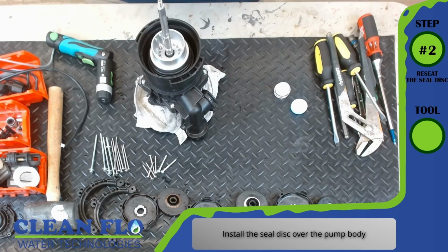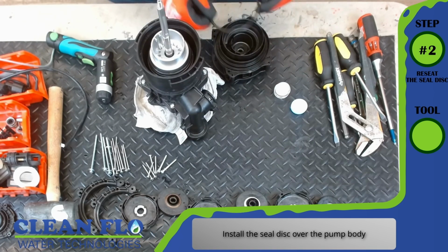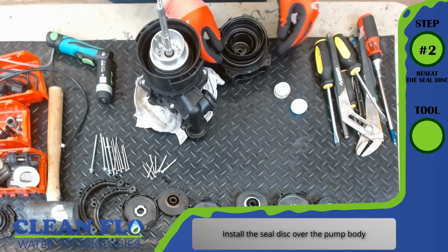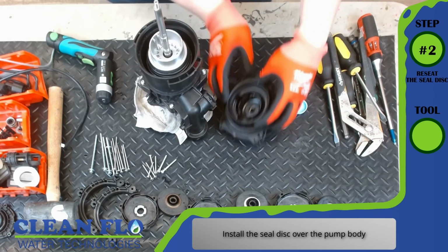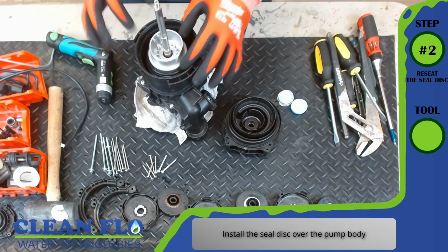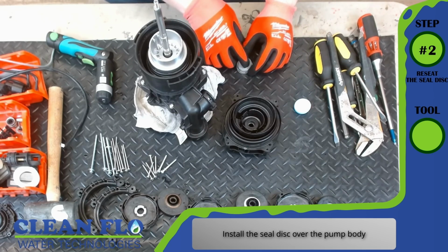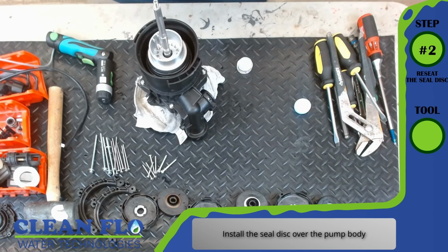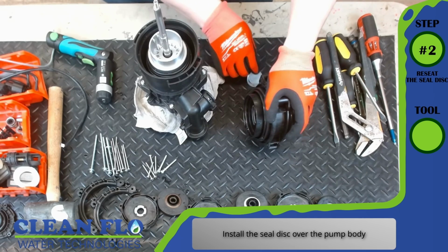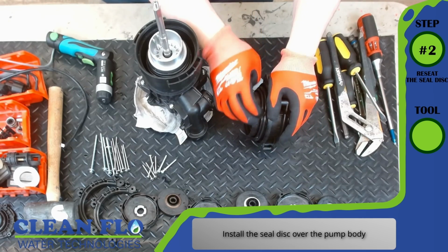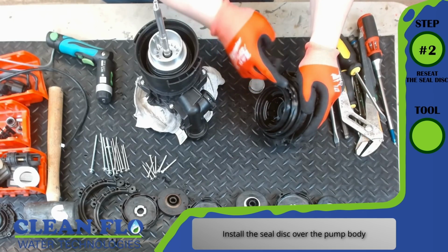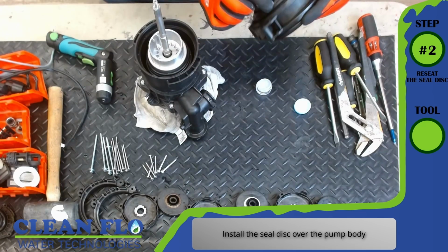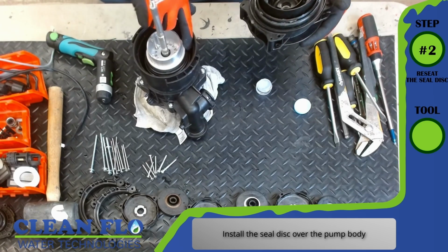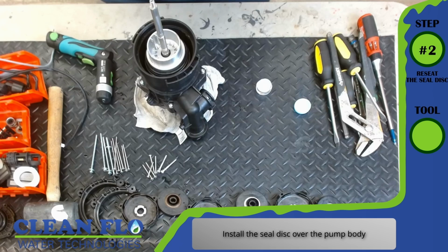Step number 2, reseat the seal disc. No tool required. Install the seal disc over the pump body. Now the seal disc actually has 2 seals on it. One of the seals is around the motor, and that's to seal the seal disc to the motor. The other is the O-ring on the actual seal disc itself, and that's to seal the seal disc to the pump body. So there's actually 2 O-rings here that we're trying to ensure are properly positioned and placed.